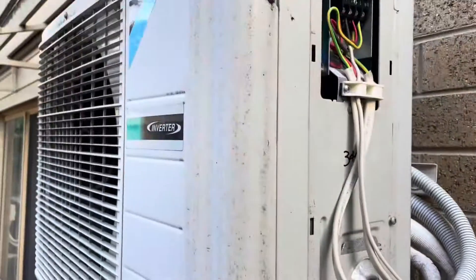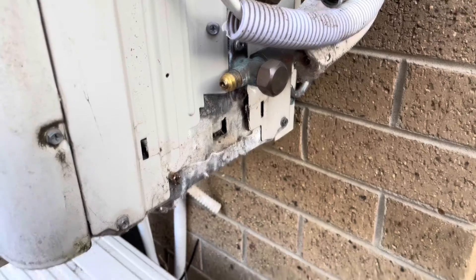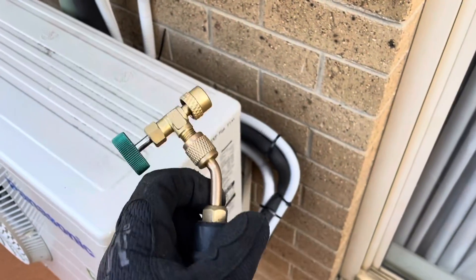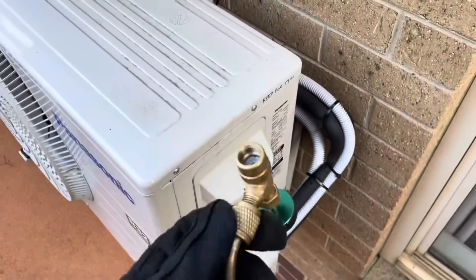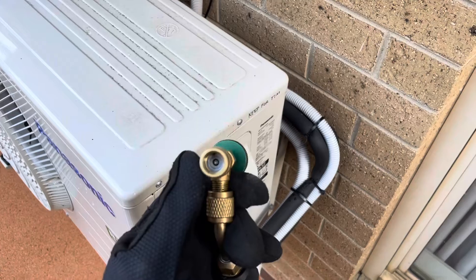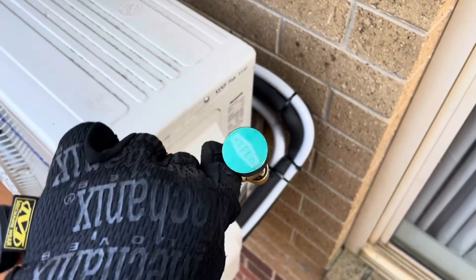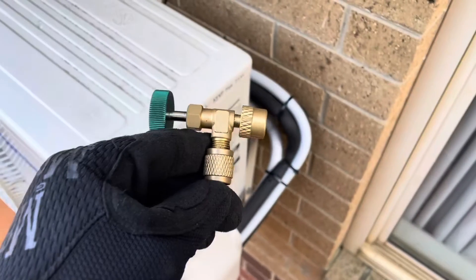We're going to start with this Daikin here. You know what works really well for pumping systems down? Probes. Now obviously the probe is a quarter-inch fitting and the 410s are 5/16s, so I've got this Schrader depressor here which is a 5/16th size, which has the quarter-inch male bit there. I think it's made by Refco — very handy.